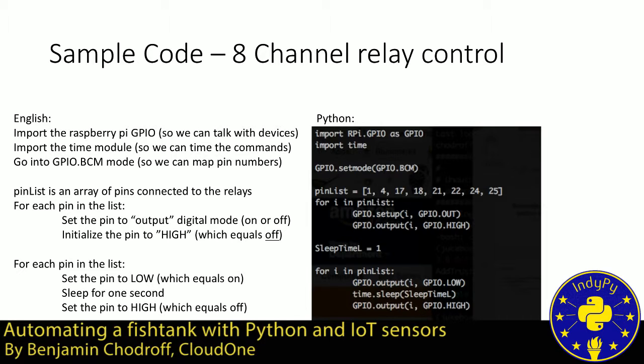Now this is counterintuitive to me, but high in this case means turn the device off to this particular relay. This allows me to say, by default, don't turn on any of the pumps. So I've just turned on the device, but I have not actually sent any voltage, or I've sent voltage which means keep the device off.